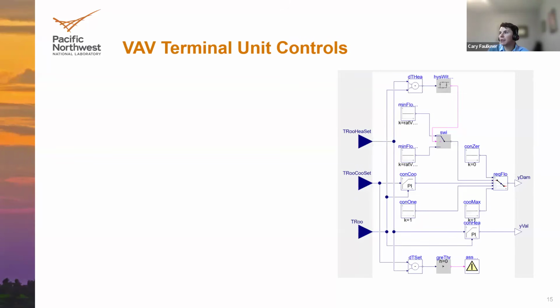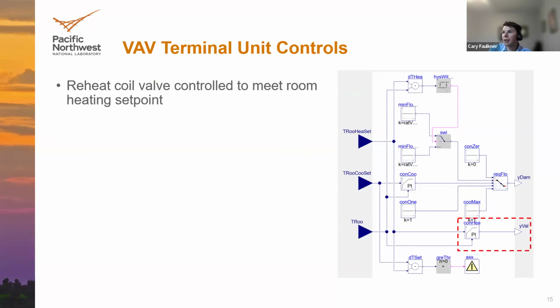So now let's talk a little bit about the terminal unit controls. We'll open up with this model block first, which shows the inputs being the room temperature set points for heating and cooling, as well as the measured room temperature. And then these are going to inform what needs to be done for the damper actuation and the reheat coil valve actuation. So let's start with the reheat coil valve. That's going to be controlled to meet the room heating set point when it's determined that heating is needed.